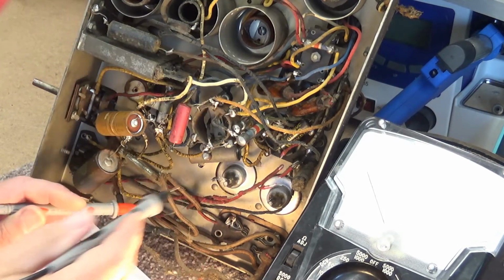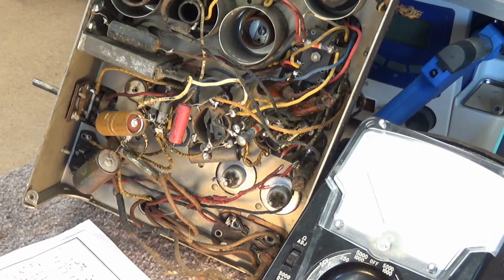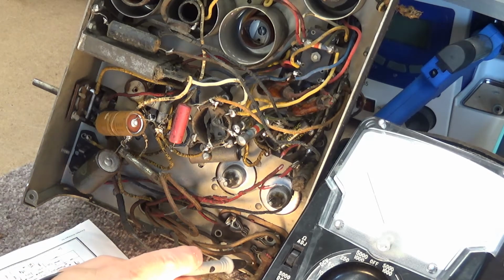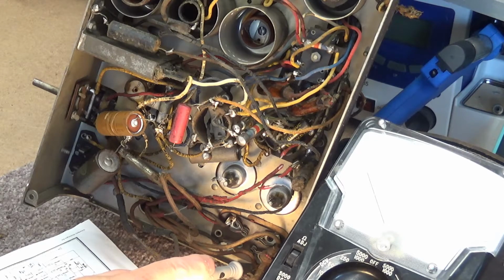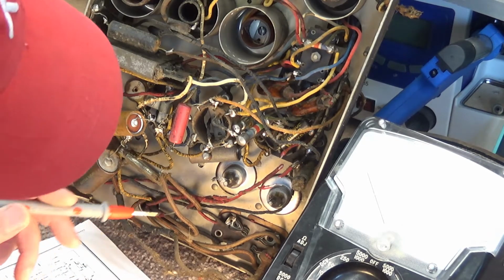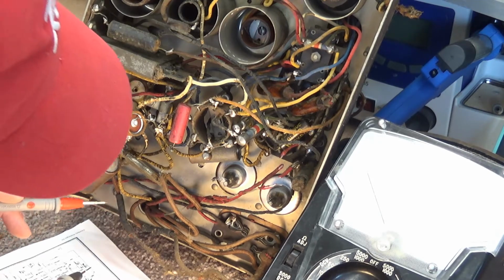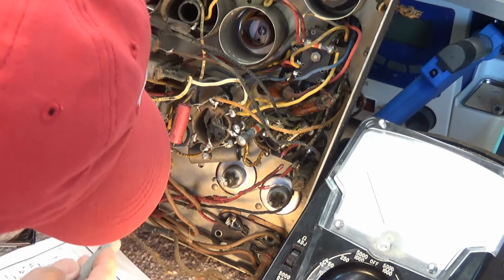I've never seen a secondary filament circuit short. Usually it's the primary that shorts. The other problem to look out for is the secondary of the high voltage being open. Usually the primary is shorted on these transformers most of the time.